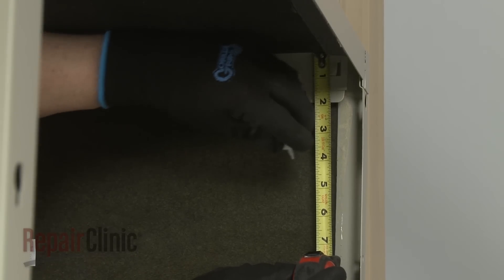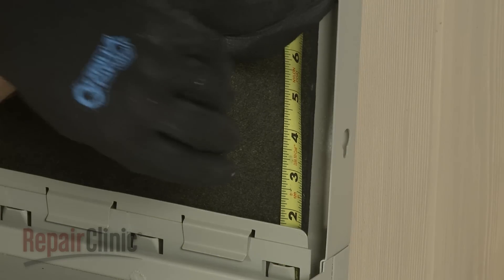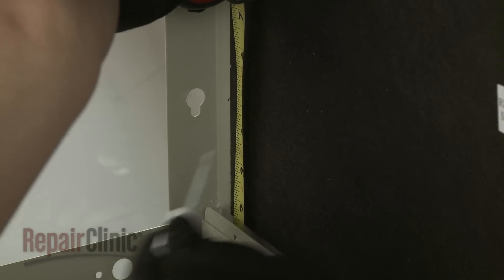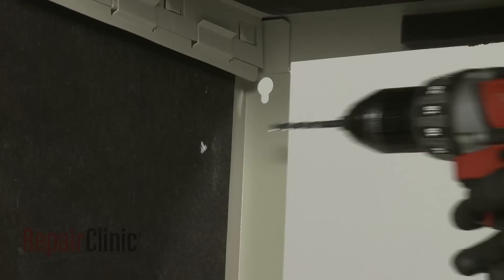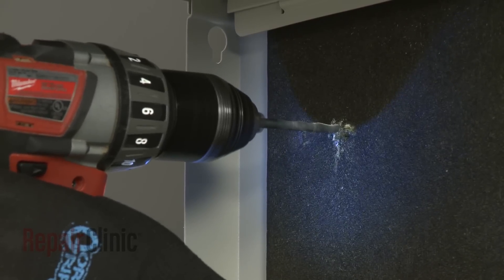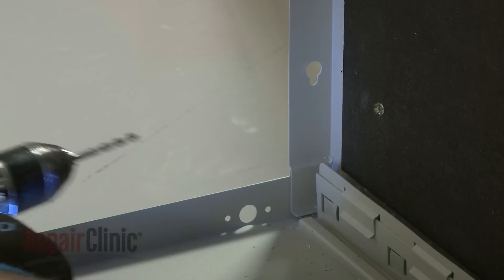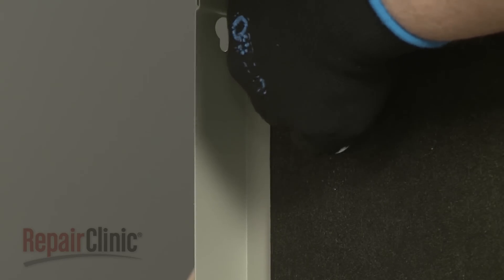Once properly positioned, determine where the wall is aligned with the sides of the sleeve, then mark two holes on each side of the sleeve, approximately 4 inches from the top and 4 inches from the bottom. Use a 3⁄16 inch drill bit to drill the four pilot holes. Use number 10 1-inch screws or the appropriate fasteners for the wall construction to secure the sleeve to the wall.